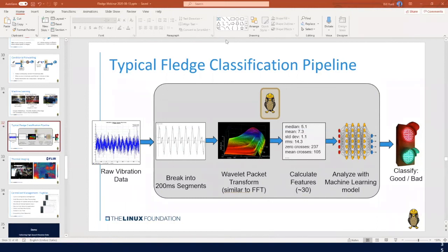Although that said, what Ashwin showed you was real. That was processing, I think, 8K samples per second of data, and it handles that just fine. So performance depends on how many sensors you want to be bringing in and how fast, and that's where you start to think about performance. Just to chime in, the plugin for the data acquisition was done in C++, so were the RMS and FFT, but the ML filter to produce good or bad bearing health analysis was done in Python. So for this demo, it's a mixture of all of those.